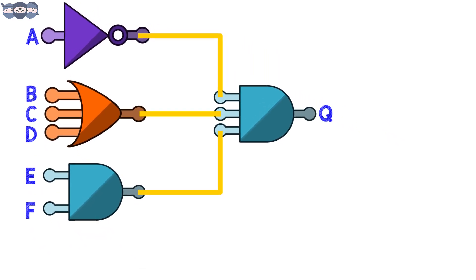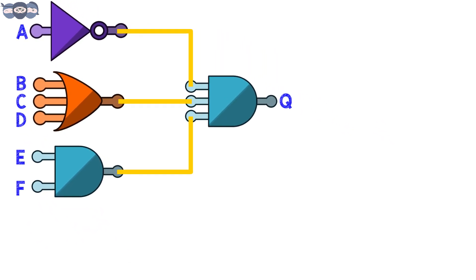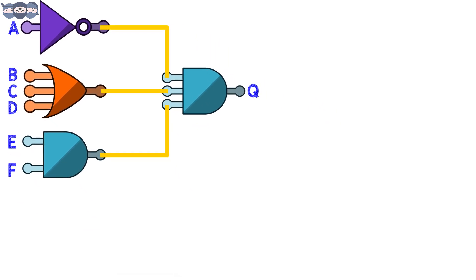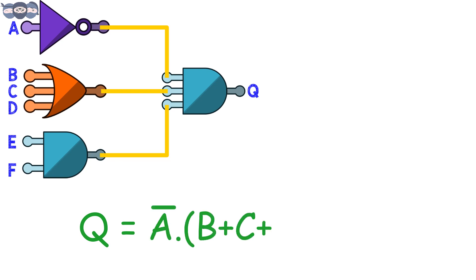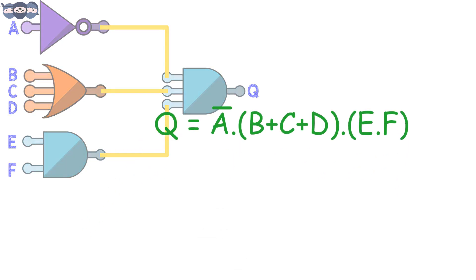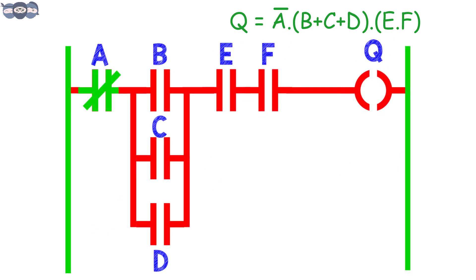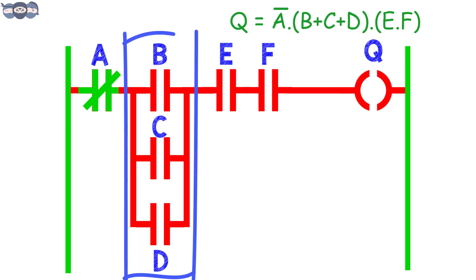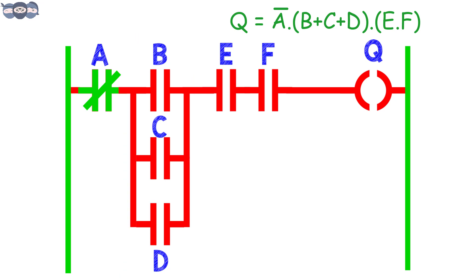Looking at the boolean logic, let us first write the expression. The boolean equation is q = ā AND (b OR c OR d) AND e AND f. The ladder logic for the equation is as follows. Here we can see that an NC (normally closed) contact is used for input a. Inputs b, c and d are connected in parallel, which forms OR logic. Inputs e and f are connected in series.